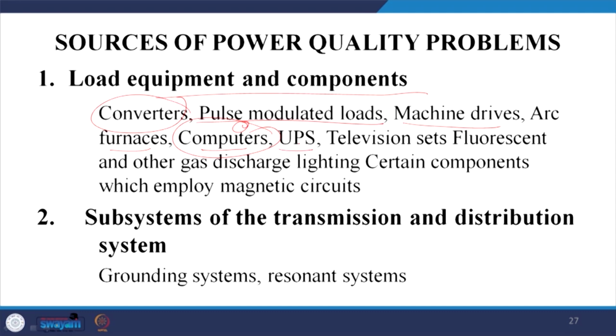Thereafter, uninterrupted power supplies, television sets, fluorescent lights, that is also a very nasty element, and other gas discharge lighting like neon, which employs magnetic circuits, so it will deteriorate the power quality. Then the subsystems of the transmission and distribution system: the grounding system is also important, otherwise ground faults will occur and earth leakage current will flow. Also in the resonance system we have to see the leakage inductance of the inductor, and when you put in a capacitor for power factor correction, that may cause a resonance at maybe the fifth or seventh harmonic, and thus those harmonics will propagate fast. So those are the issues we need to address and mitigate.